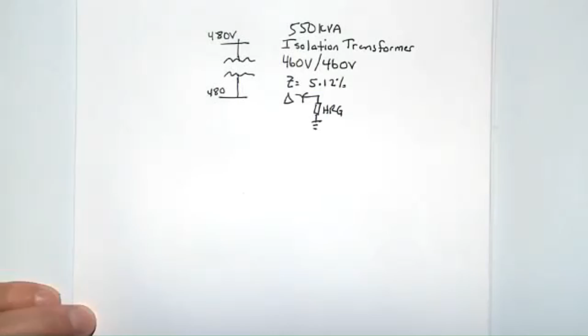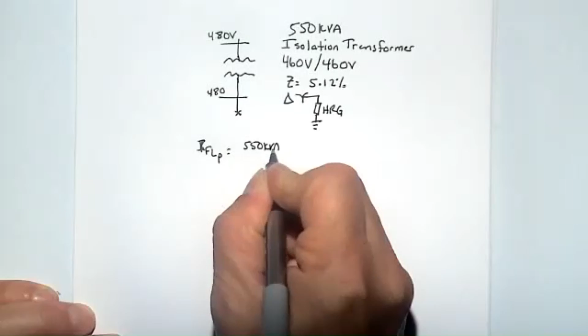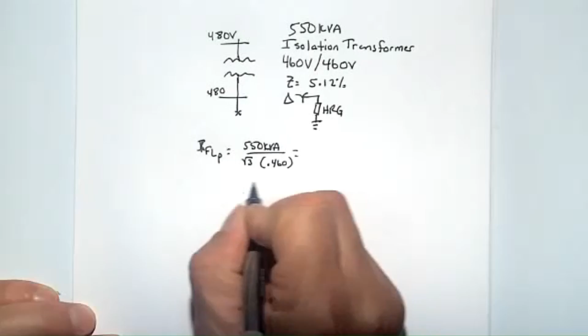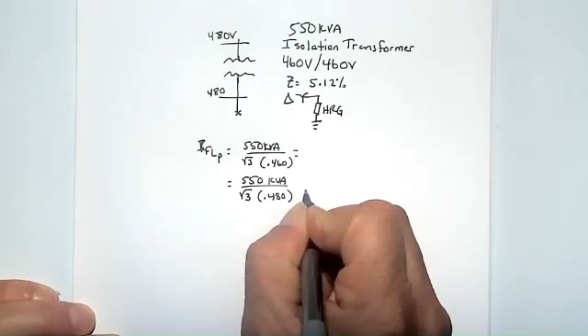So again, we'll start with our same equation we've been using the whole time here, which is I full load primary, and in this case it's going to be the same as secondary, coincidentally because the voltage is the same. It's going to be 550 kVA divided by square root of 3 kV line to line. Now the tricky part is, do we use the rated value or do we use the actual applied voltage? And what I'm going to tell you here is, let's do it both ways. Let's do 460, and then we're going to do the same thing, 550 kVA divided by square root of 3 times 0.48, and let's just see what the difference is there. So 550 divided by 1.73 divided by 0.460.